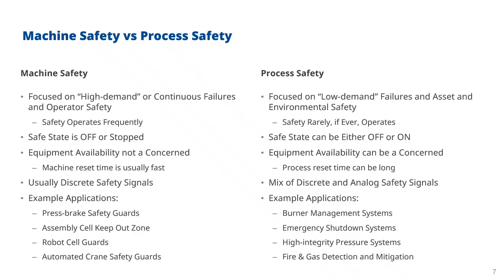Process safety is quite different. It's focused on low demand failures, and the focus is not just on the operator, but it's also on the asset or the equipment, and also on environmental safety. Now, unlike machine safety, with a process safety system, ideally it will never operate. If you have an issue where the process safety trips the plant or shuts down the plant, something has gone seriously wrong. There's been an oil leak or a gas leak or something else has happened.